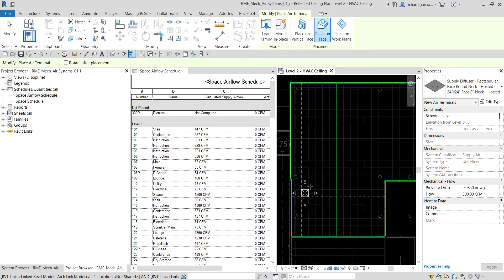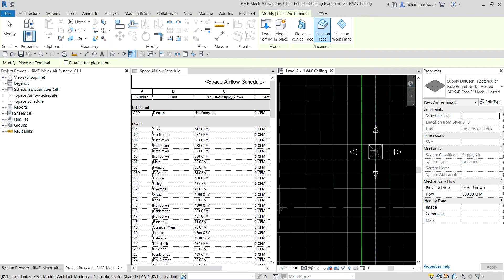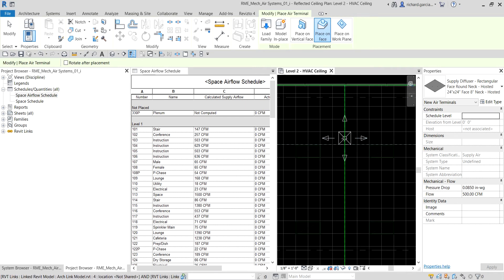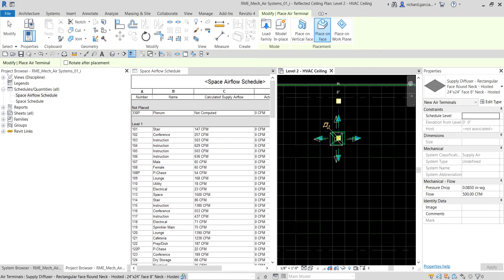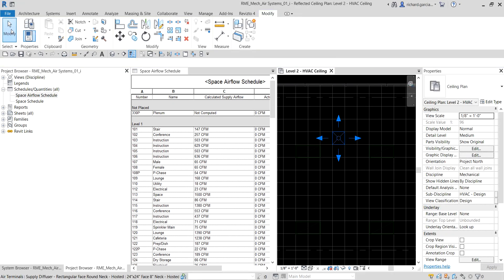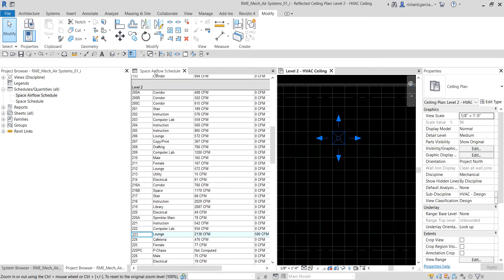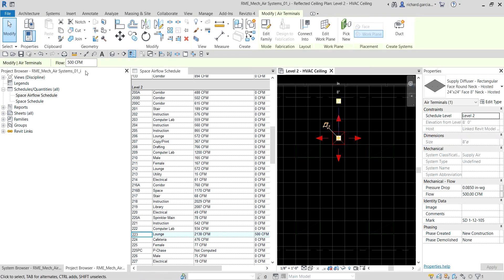I'll place it somewhere on the ceiling — there you go. I then select Modify to terminate the placement. Notice that going back to the space airflow schedule, the actual supply airflow has now updated to 500 because the default airflow for this diffuser is 500 CFM.